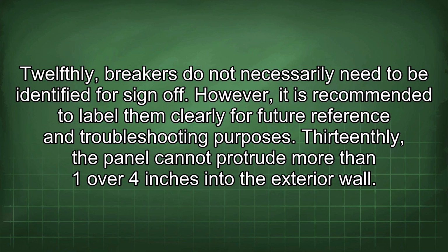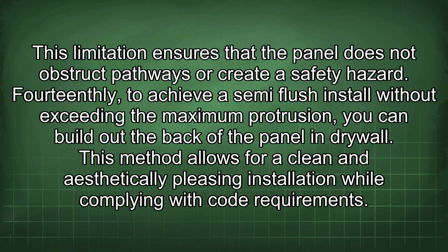13thly, the panel cannot protrude more than 1/4 inches into the exterior wall. This limitation ensures that the panel does not obstruct pathways or create a safety hazard. 14thly, to achieve a semi-flush install without exceeding the maximum protrusion, you can build out the back of the panel in drywall. This method allows for a clean and aesthetically pleasing installation while complying with code requirements.